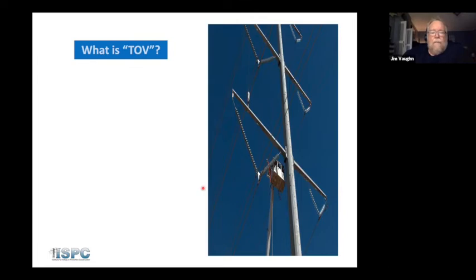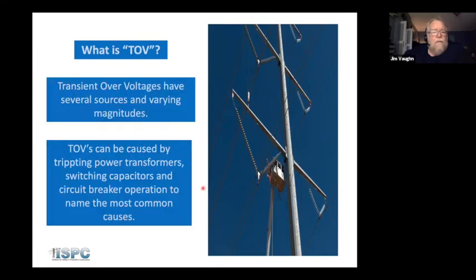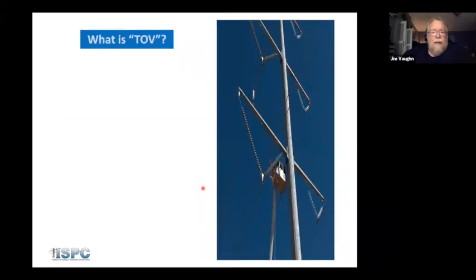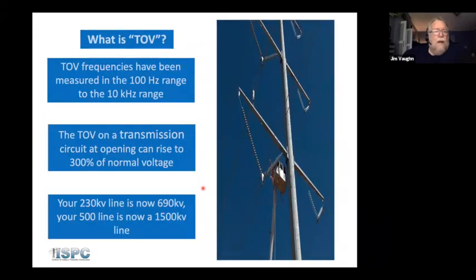Now, here's what the TOV is. Transient overvoltage has several sources and varying magnitudes. They're caused by tripping power transformers, switching open capacitors, and circuit breaker operation are the most common causes, and I'll explain why that is in just a minute. In a TOV, frequencies have been measured in the lab at 100 hertz to 10,000 hertz range.